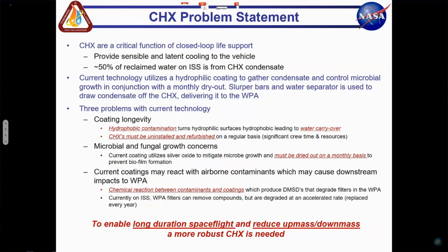There are 3 big problems with the current technology. One is coating longevity. Hydrophobic contamination causes that hydrophilic surface to turn hydrophobic, and you get water carryover, so water spits out of the heat exchanger and potentially damages downstream components. Because of that, your heat exchanger ORU has to be uninstalled, brought back down to earth, refurbished, and then sent back up. That is a very significant resource drain.